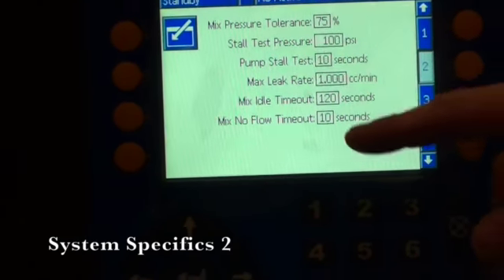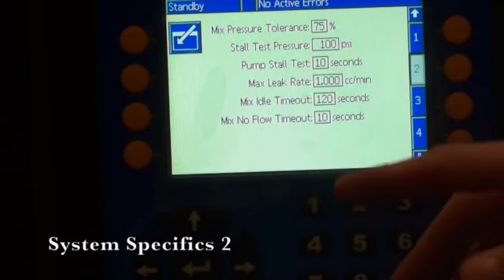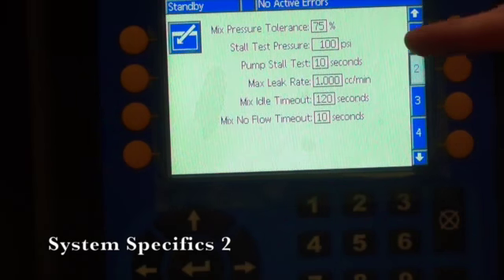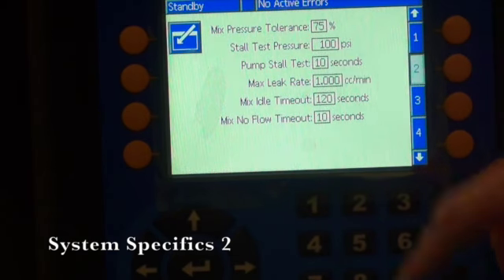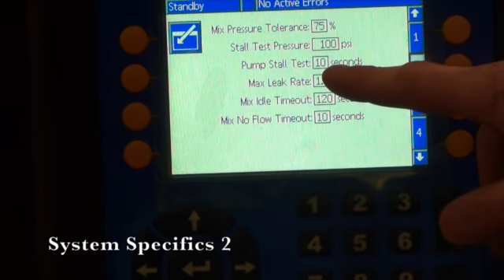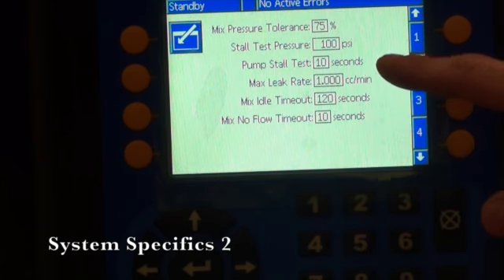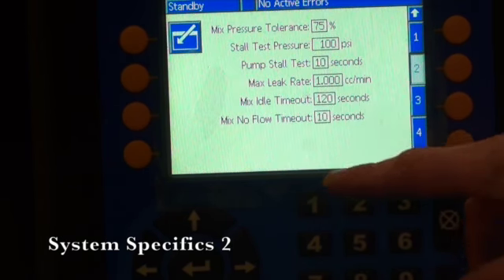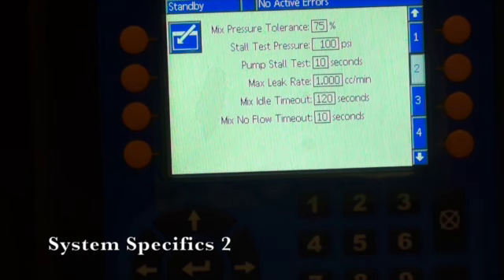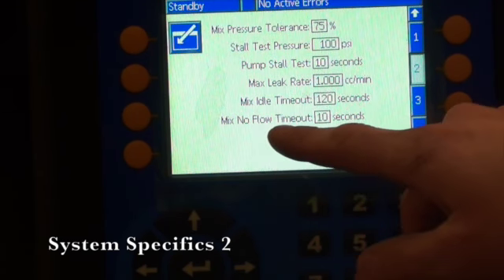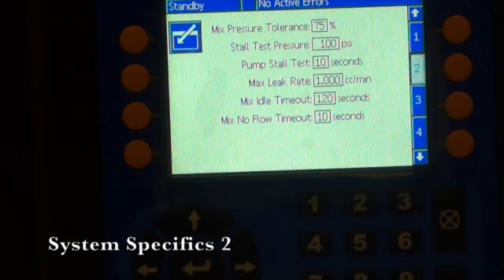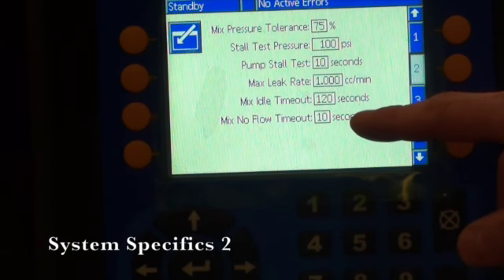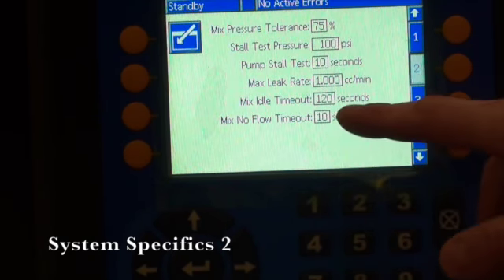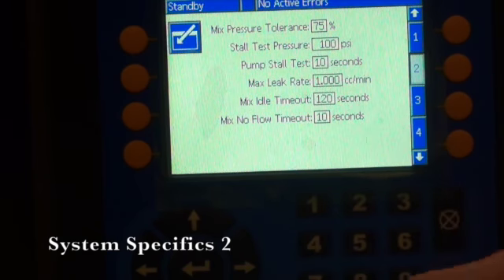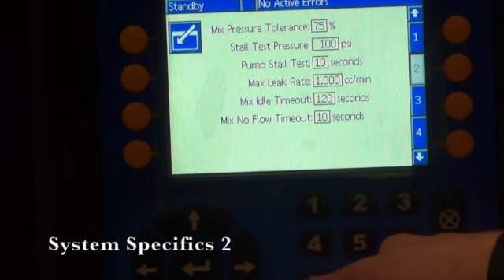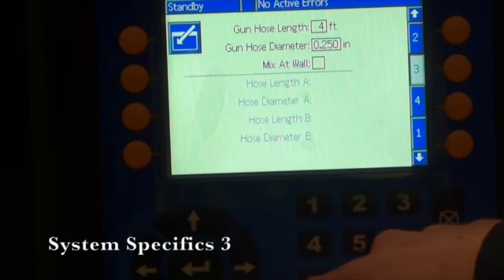Down further is where you put in your tolerances. Right now, since we're running solvent, we have it set at 75%. Stall test pressure of 100 psi. Stall test is 10 seconds. And then down through here, we have our idle timeout and our mix no flow timeout, which is 10 seconds. If the system does not detect flow and it detects air, it's going to alarm out. These can be set once you get your pumps loaded and you figure out how your operators react.